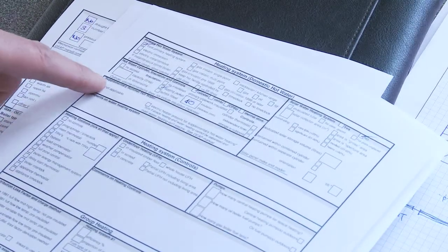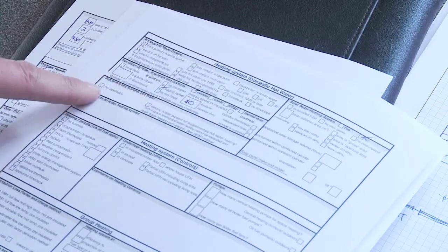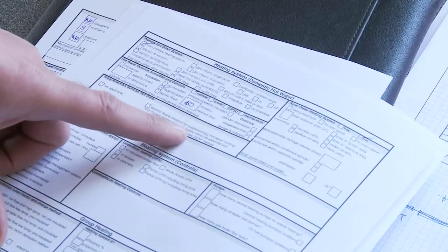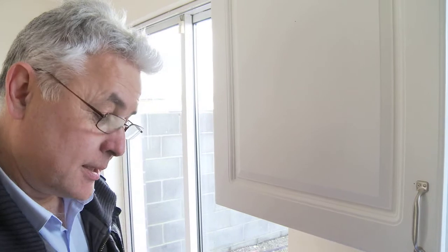It asks, is supplementary summer hot water applicable, or is there an immersion heater present? In this situation here, we cannot separate the hot water from the main boiler. We cannot just heat hot water and not heat radiators. We don't have the correct level of controls to do that. So we will be putting into the software that this particular house does use supplementary electric hot water during the summer. So in this box here, we'll just give that a tick just to remind us when we get back to the office that we have to do that.